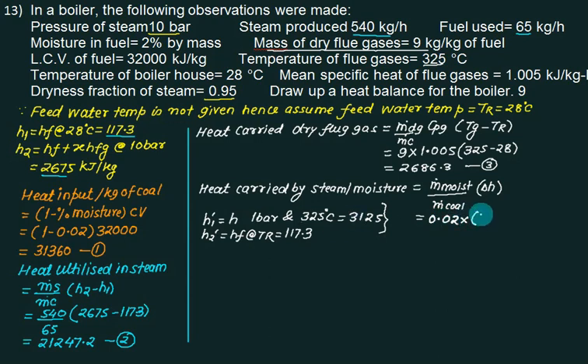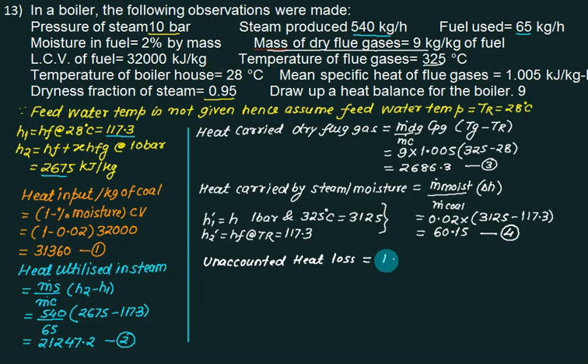All data exhausted. Any unburnt fuel? No. Unaccounted heat loss equals item 1 minus 2 plus 3 plus 4, which gives 7363.8 kilojoules per kg of coal. I suppose this is better compared to the last problem which was 10,000. It's improved now to 7000. After this, you have to prepare a table, that is compulsory.